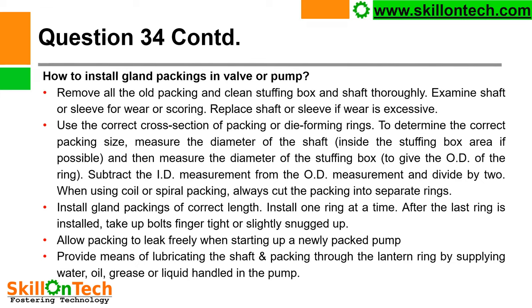When using coil or spiral packing, always cut the packing into separate rings. Install gland packing of correct length, install one ring at a time. After the last ring is installed, take up bolts finger tight or slightly snugged up, and then finally tighten the gland follower bolts by a spanner. Allow packing to leak freely when starting up a newly packed pump. In the starting of the pump, allow some water to leak from the stuffing box to provide cooling to the gland packings and to let them well set. When once it is set and there is no smoke from the gland packings, slightly tighten the gland follower bolts. Provide means of lubrication through the lantern ring by supplying water, oil, grease or liquid handled in the pump.